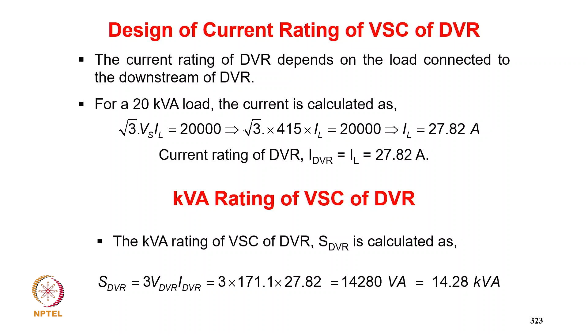Now rating of injection transformer. The injection transformer is designed considering the optimum voltage level of the VSC, and the kVA rating of the injection transformer is the same as that of the DVR rating, calculated as kVA equal to 3 VDVR IDVR upon 1000. So it comes to 14.28 kVA and 550 volt divided by 170 volt. The voltage rating of the secondary winding is considered as 50 volt.